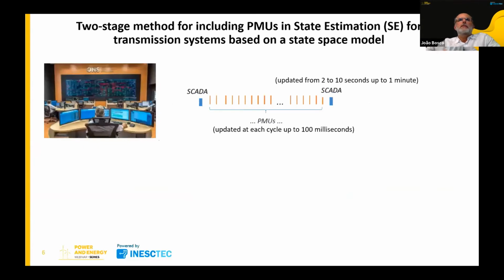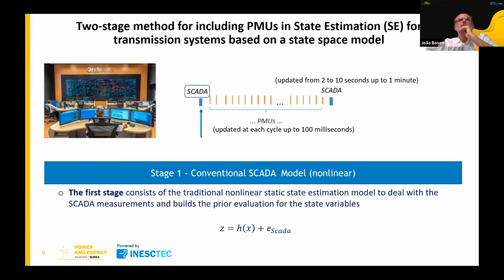This figure illustrates the updating time interval of SCADA and PMU measurements. Observe that between two SCADA data samplings, there are several PMU data that can be used for state estimation, but not at the same time. The estimation process in each stage initializes as soon as the respective measurement sample becomes available. So, when a SCADA sample becomes available, stage 1 is initialized and consists of the traditional nonlinear static state estimation model to deal with the SCADA measurements and build the prior evaluation of the state variables.